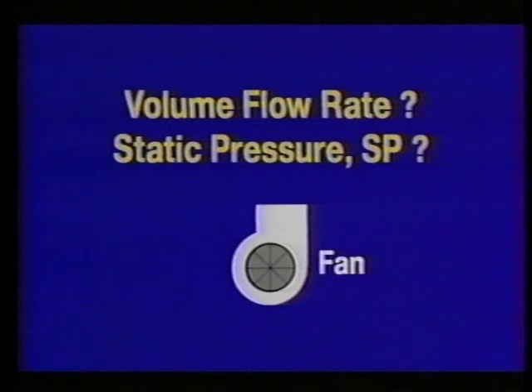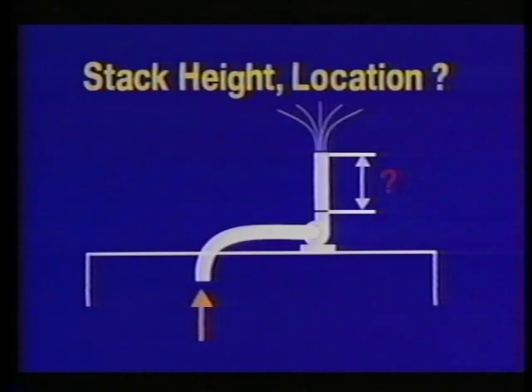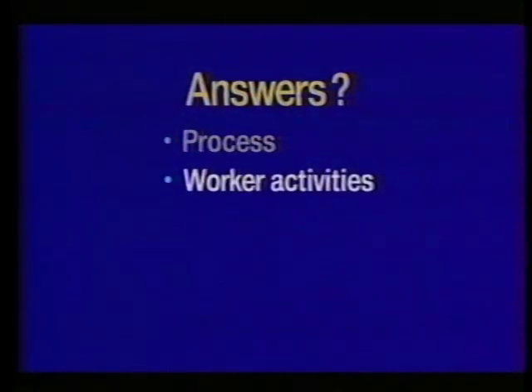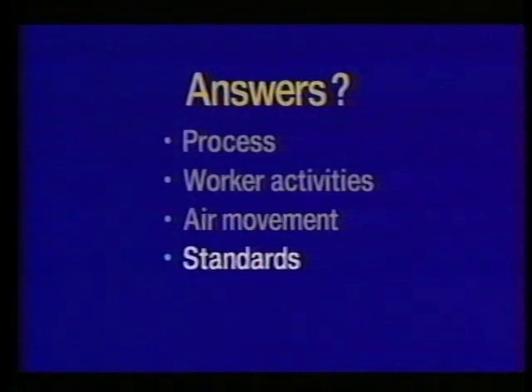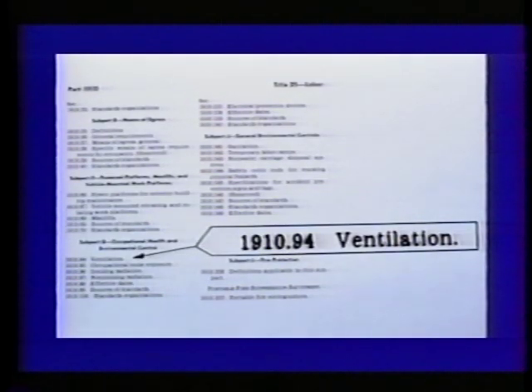How large should the fan be? Fans are chosen to match the requirements of the exhaust ventilation system — the fan must move the correct volume of air against the resistance caused by friction and turbulence. The designer will estimate the static pressure required. How high should the stack be and where should it be located? The stack must be high enough or far enough from intakes to avoid re-entrainment of contaminants into the building air handling system. These questions are answered through careful study of the industrial process, worker activities, air movement in the workplace, and by searching design references for appropriate standards. OSHA has included some design criteria in its ventilation regulations.